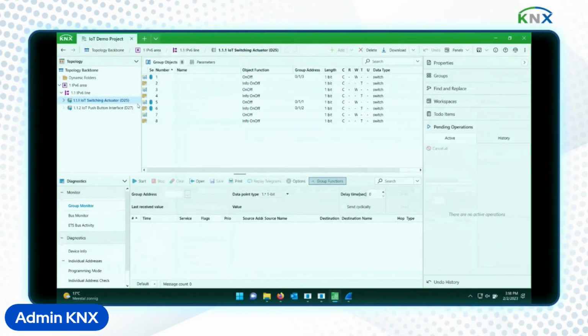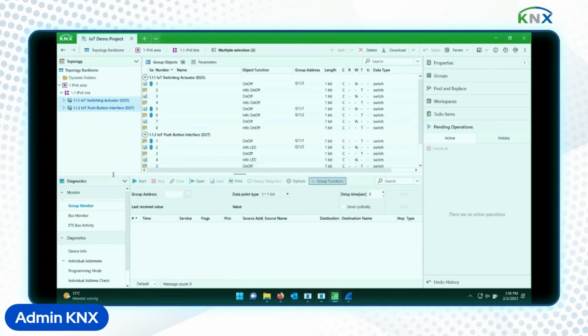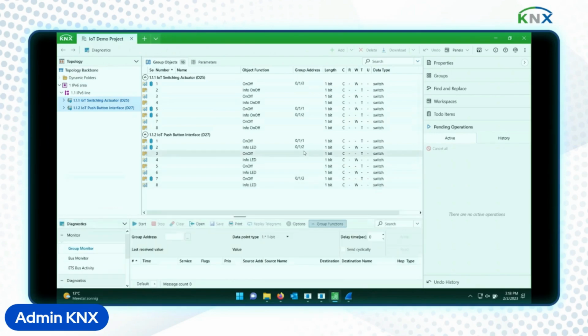what I have here is a representation of those two devices in ETS so that I can use their objects and link them by means of group addresses. And by that, I then create functions. If I check closely, I have created here a function where the push button channel 1 is operating upon channel 3 of the switching actuator. So a bit different function, which is maybe a good example in this case. Let's see if I can get it working.